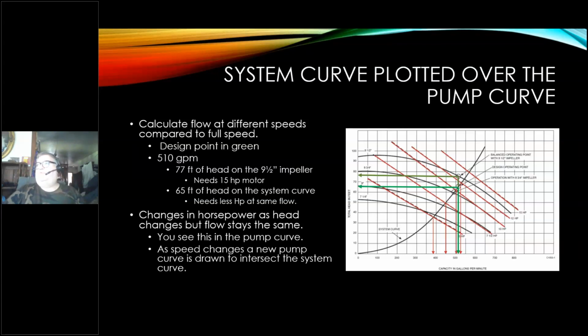So in this case, the design point's in green. I'm doing 510 GPM, 77 feet. On the 9.5 impeller, it needs a 15 horsepower motor. 65 feet of head on the system curve. This is the actual system curve. It needs less horsepower at the same flow, so the resistance restricted or cut back your system flow or your system curve. But it needs less horsepower at the same flow just because of where it lands on the system curve. Okay, this is your actual system. Changes in horsepower as head changes, but flow stays the same. You see this in the pump curve.